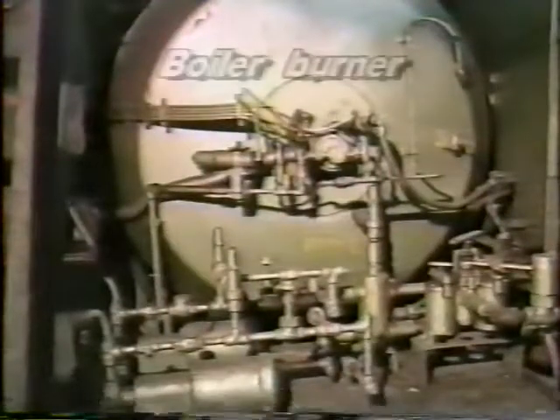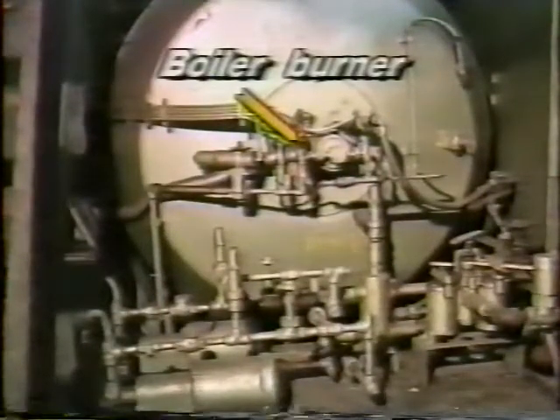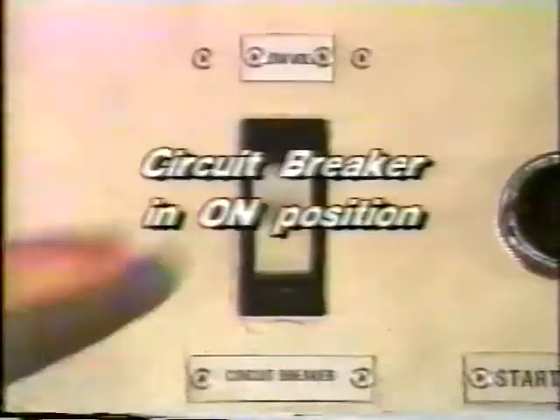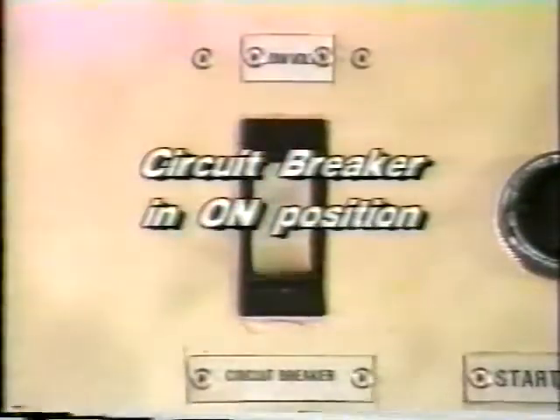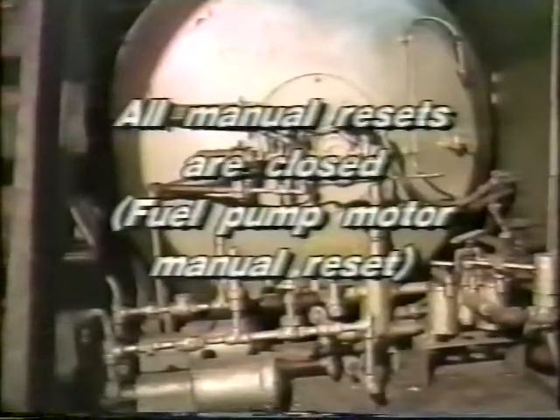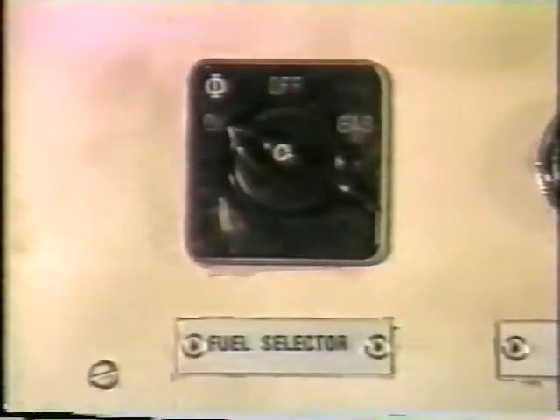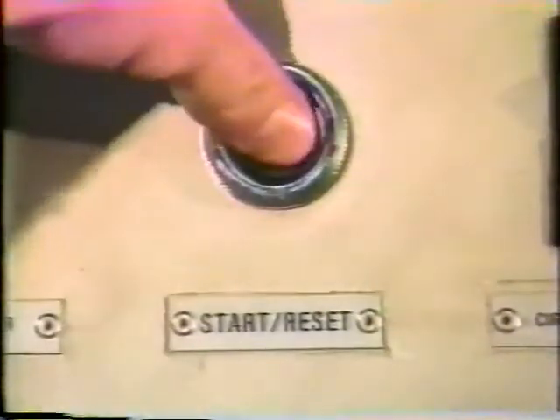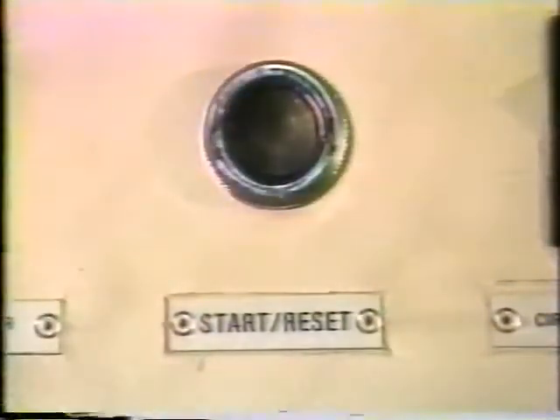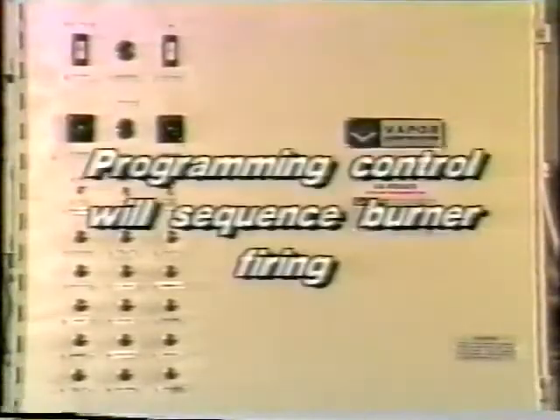Firing the burner. If the burner is to be fired immediately after the boiler is filled, the operator simply leaves the main power switch closed and the circuit breaker in the on position. All the manual resets are closed and the fuel switch is placed in the oil position. Next, the start reset switch is pressed. At this point, the programming control will take over and automatically sequence the firing of the burner.